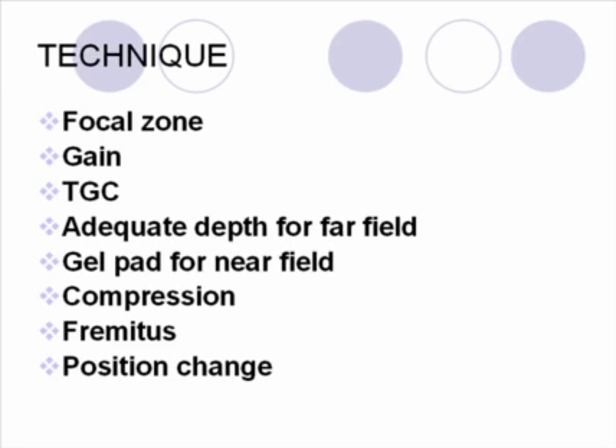Most modern equipment, focal zones will cover that area, but if you feel like your focal zone isn't really getting to the area that you're seeing, if it's that superficial, use a gel pad, which will bring your focal zone into the zone of the mass. Other things such as compressing the mass to see if it's compressible, elastography, fremitus, position change to see if the mass changes position, all these things can also be used, but more often it's just your basic things that you use with other forms of ultrasound, making sure your focal zone is right, making sure your gain settings are right, and making sure your depth covers the area that you need to see.